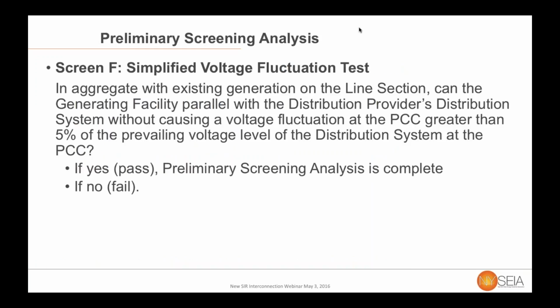The last of the preliminary screens is screen F, the simplified voltage fluctuation test. It simply asks, can the generation parallel with the system without driving the system more than 5% off the prevailing voltage? And it's important to recognize that superseding all of these requirements is that Section 2 requirement that says you must retain the voltage within the ANSI limit. So even though it says at prevailing voltage, if this is a point where your voltage is already low, for instance, if 5% would drive you out of ANSI limits, that's a requirement that sits on top of these screens. And so the application of this will generally be that 5% of prevailing, but it is important to recognize that superseding requirement that lives in Section 2.